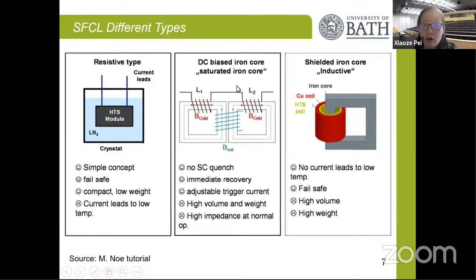When the magnetic core is connected to the power grid, you can consider it an air core because it is in the saturation stage, so there is very low inductance connected to the grid. When the fault happens, the fault current drives the magnetic core out of saturation, which now becomes a high inductance added into the circuit to limit the fault current. In this process the superconducting tape is not quenched, which means it can have a faster recovery stage. The quench is the stage where the superconducting tape transitions from the superconducting state to the normal state.